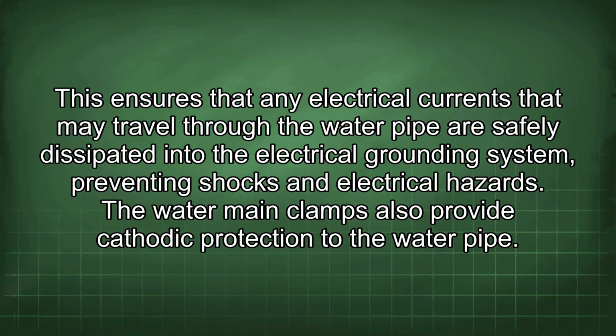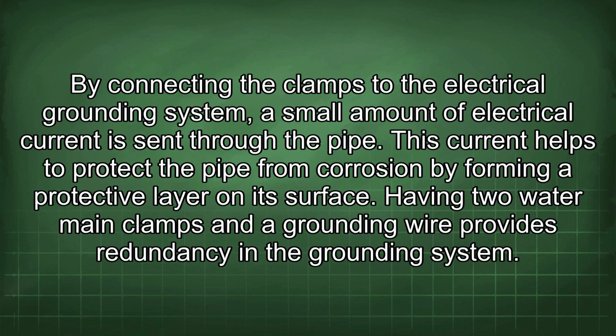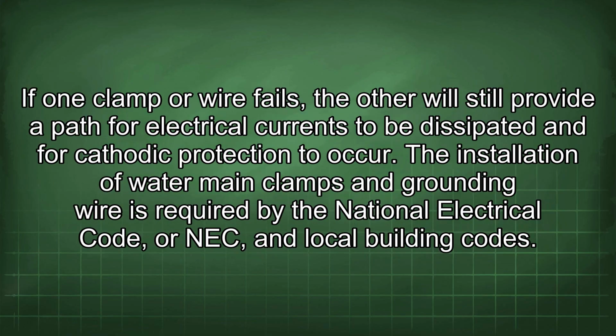The water main clamps also provide cathodic protection to the water pipe. By connecting the clamps to the electrical grounding system, a small amount of electrical current is sent through the pipe. This current helps to protect the pipe from corrosion by forming a protective layer on its surface. Having two water main clamps and a grounding wire provides redundancy in the grounding system. If one clamp or wire fails, the other will still provide a path for electrical currents to be dissipated and for cathodic protection to occur.